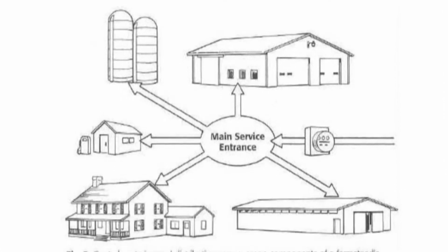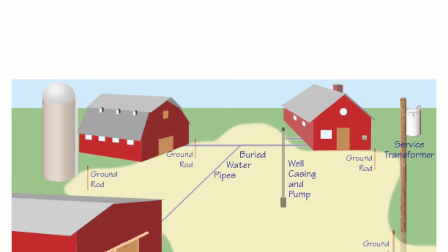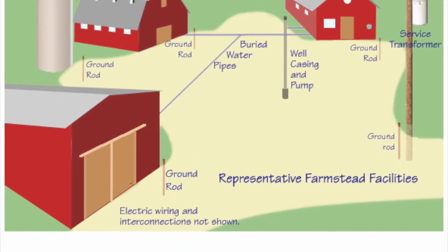The modern farm must be equipped with an electrical distribution system that complies with regional safety standards, meets the needs of the farmer, and leaves room for future expansion and modernization, all while minimizing operating cost. When faced with farmstead electrical distribution planning, the individual must take the following steps to meet all of the aforementioned requirements. Number 1. Determine the demand load for each service location on the property.